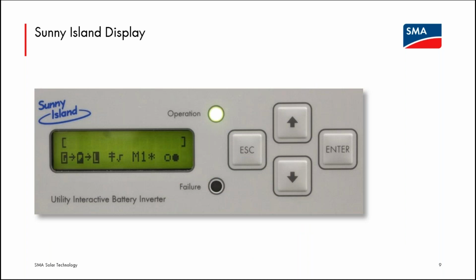The display of the Sunny Island is shown here with the up, down, escape, and enter keys. All of the programming of the system is really done from the front of the master device. If you have more than one Sunny Island, one will be the master, all the rest will be designated as slaves, and they all just take commands from the master and run the system in accordance with what the master says. So really all of the programming is done from the front of the master device.